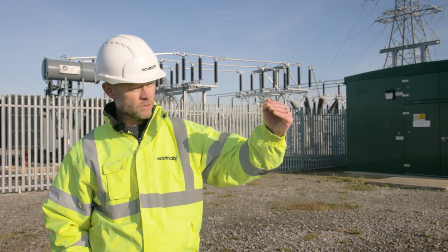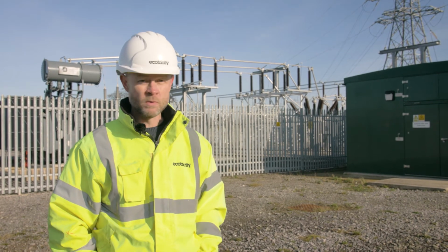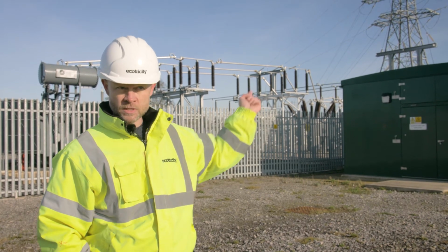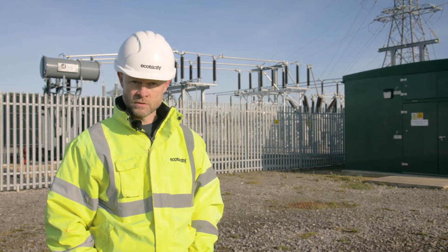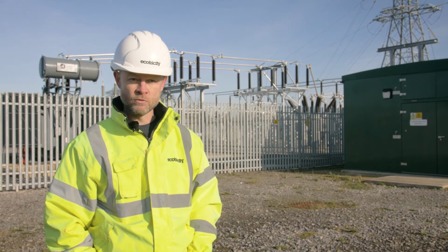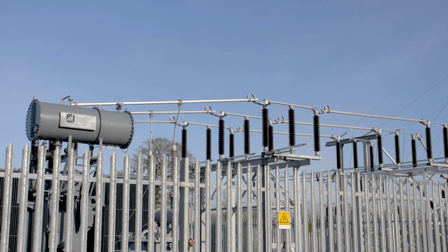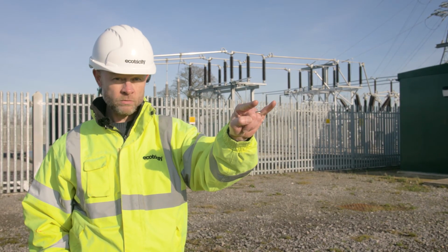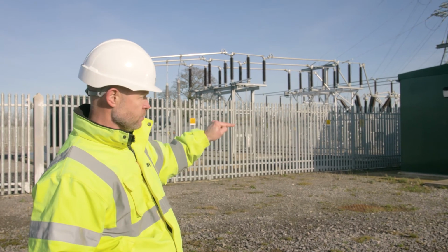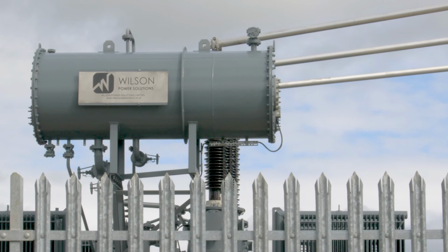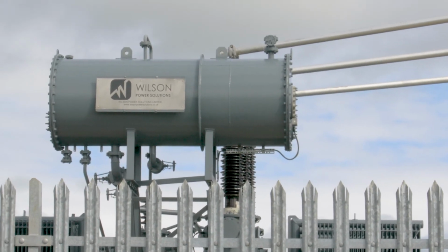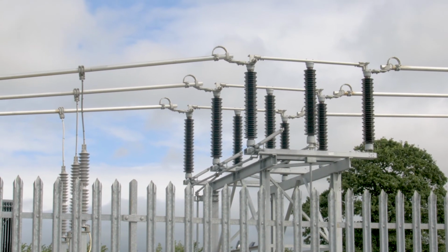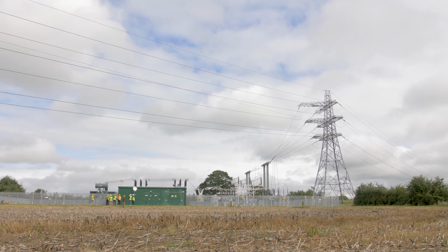So all the communication and all the control systems that are on the windmills, that data is transmitted via fibre optics to this point here, and then transmitted to our service team so they understand how the windmills are performing. Inside the substation, behind me, is the big transformer. We generate at 11,000 volts from the windmills, through the cables, up to this point here, through the meter, into the transformer, which steps it up to 132,000 volts in this case, and then transmits over into Western Power Distribution's side, and then on to the network, and then away.